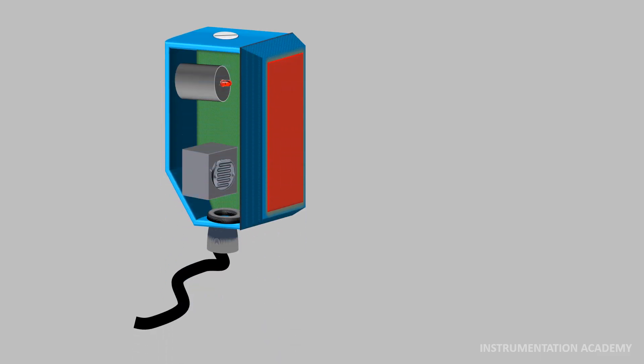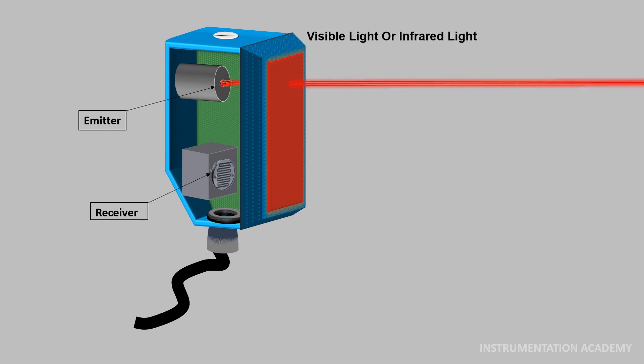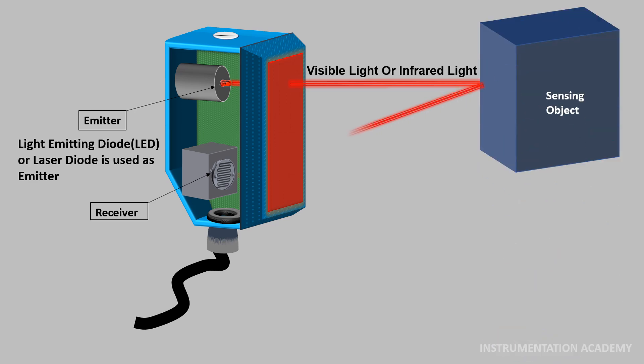A photoelectric sensor basically consists of an emitter for emitting light and a receiver for receiving light. The emitter converts the electrical signal to light energy and emits a produced light as a beam of either visible light or infrared light. Usually, LED or laser diode is used as emitter. When emitted light is interrupted or reflected by the sensing object, it changes the amount of light that arrives at the receiver.